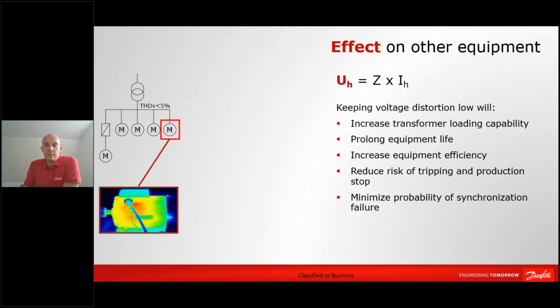The problem with harmonics is, however, not on the current. The problem with harmonics is actually due to the voltage. So if you look at your normal system supply, you will see that you have maybe one drive supplying a motor, and then you have a lot of direct online motors supplied from the same transformer. If you take this example you have on the right, we have one drive only. We have a voltage distortion of 5%, and you can see the direct online motor that is pulling the supply power from the transformer is fairly cool. So if you look at the picture here of the motor, you can see that the motor is not heated up. It's not very red, indicating that the motor is quite cold. The motor is having good running conditions.